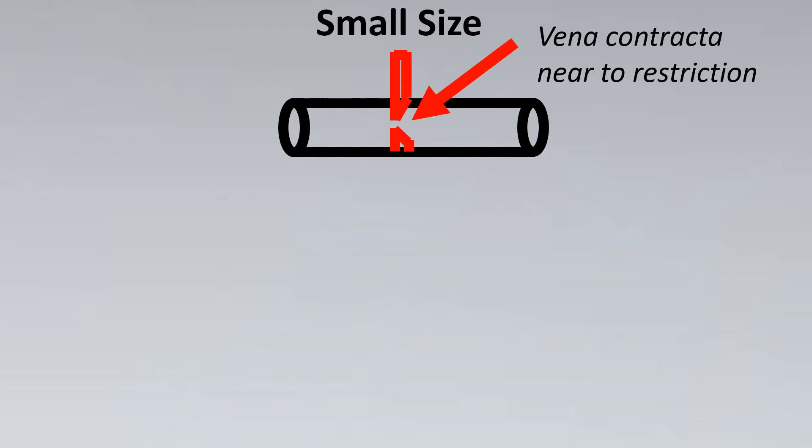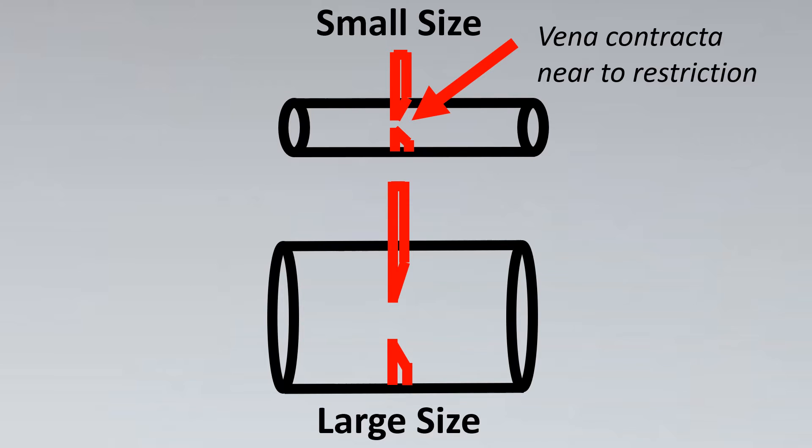This concept depends upon line size. So for smaller line sizes the Vena contracta is near to the restriction. However, for larger line sizes the Vena contracta would be away from the restriction. Does that have any issue on our tapping selection? Absolutely, it has an effect on the selection.